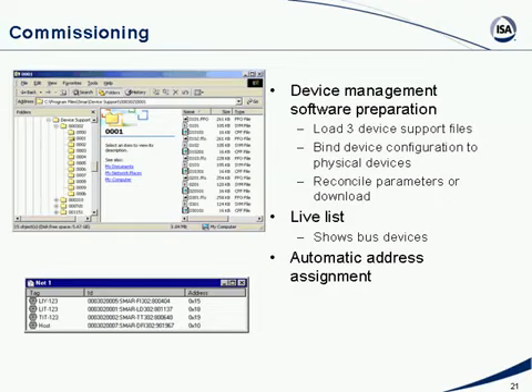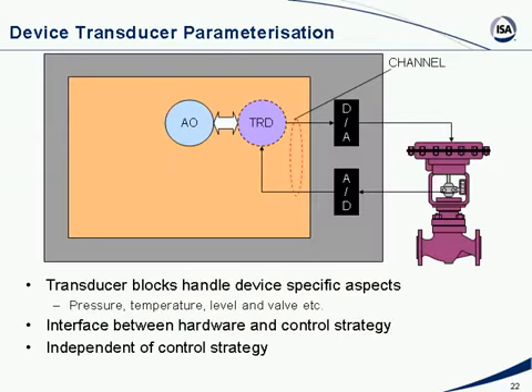Okay. So if a device doesn't show up in this list, it either means it has not been connected, or connected to the wrong bus, or there is something seriously wrong with the device. Anytime a device stops communicating, it drops out of this list. Anytime you connect a new device to the bus, it shows up in this list. Okay, so it's a very useful troubleshooting tool, very useful for commissioning. So this live list takes the place of the traditional ringing out of wires. Okay.